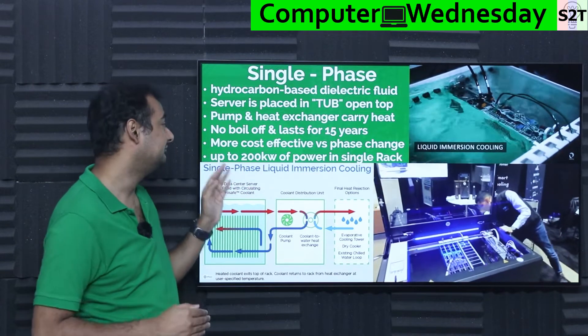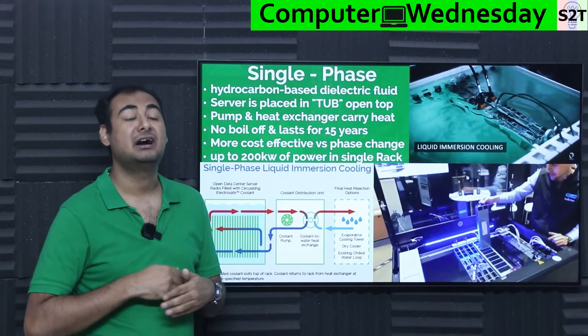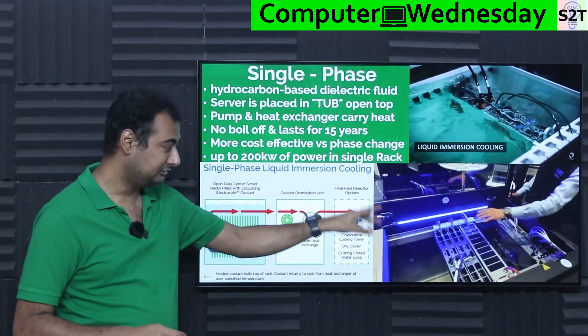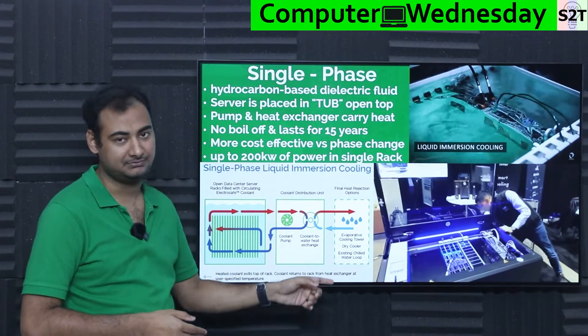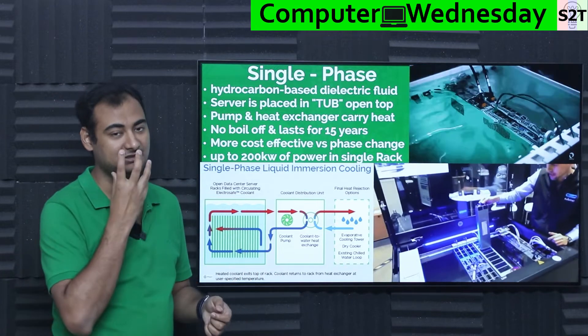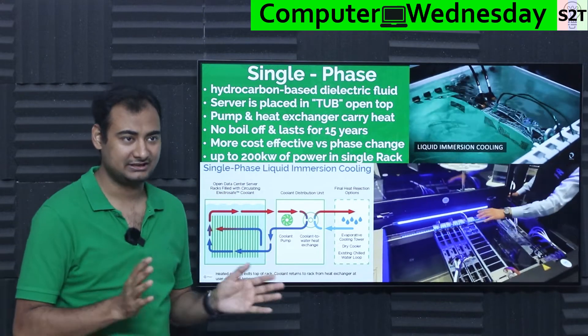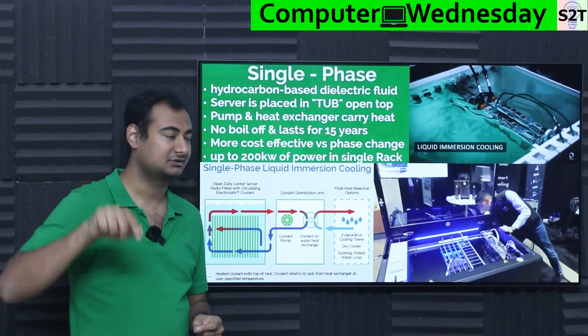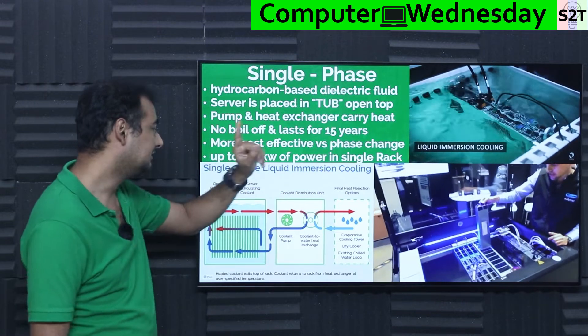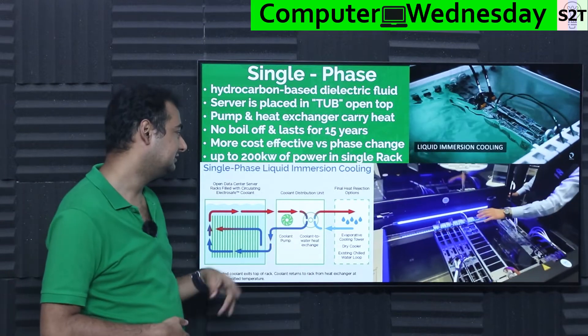Because the fluid is not boiling off, you can achieve a 15-year lifespan. This fluid is far cheaper compared to fluorocarbons and lasts far longer. There is no boil-off and it is far more cost effective — per unit of server it will be cheaper, exponentially cheaper. Gas-tight chambers are not cheap, and every time you open one you have to give people a gas mask. Single-phase is just a tub — a person could theoretically swim in it, although not recommended.